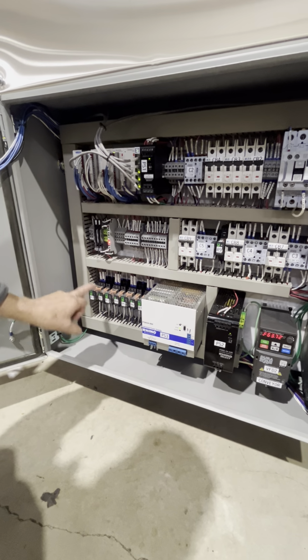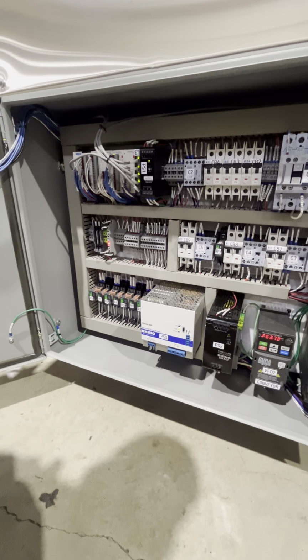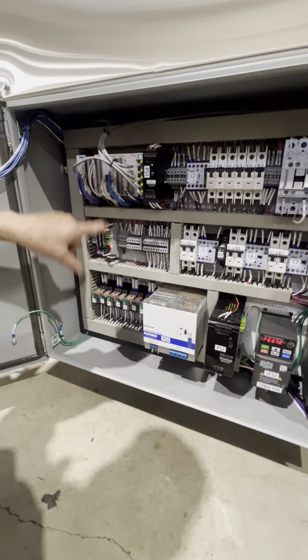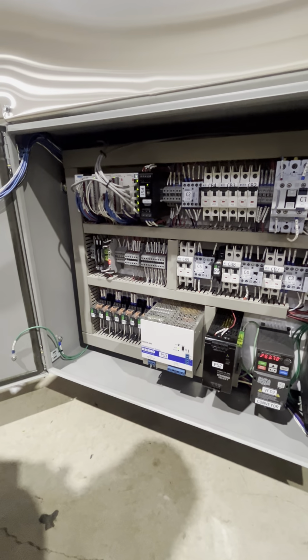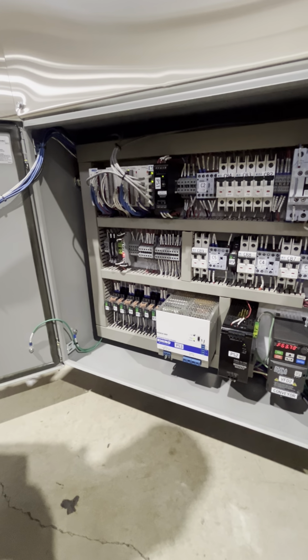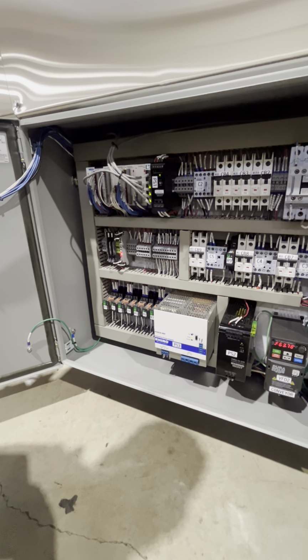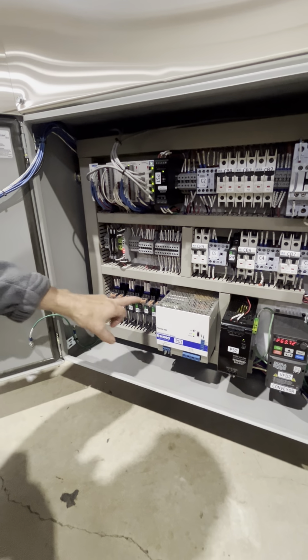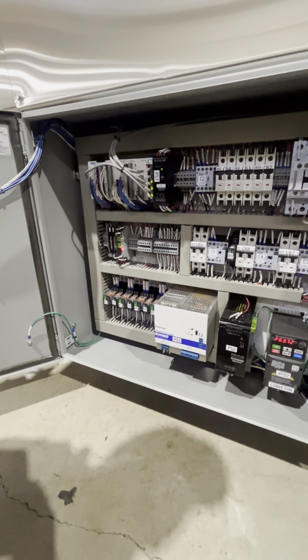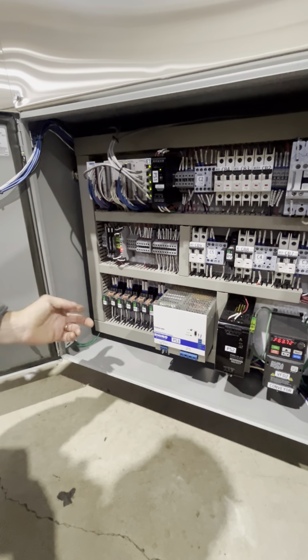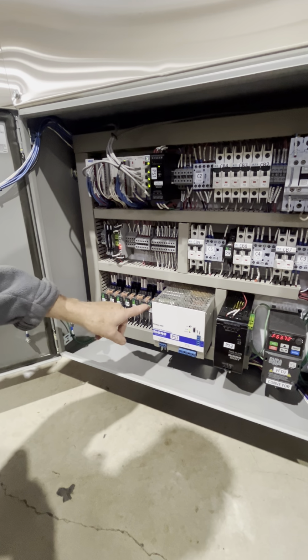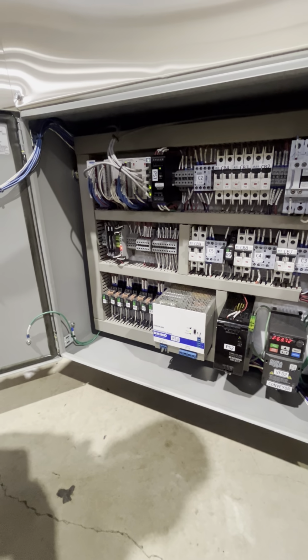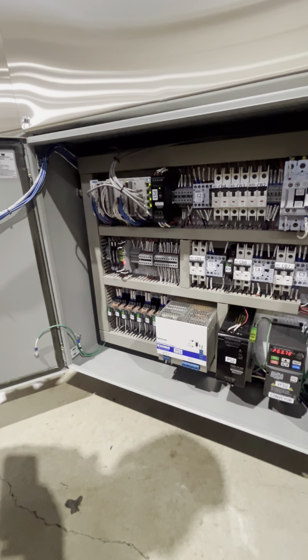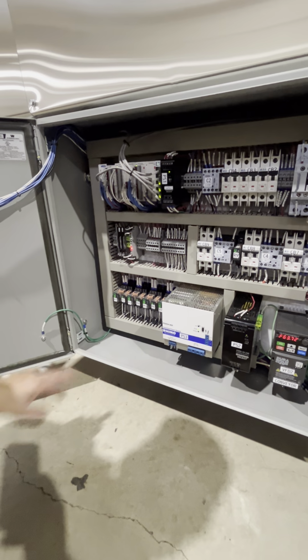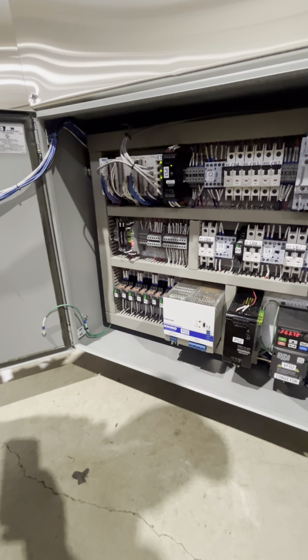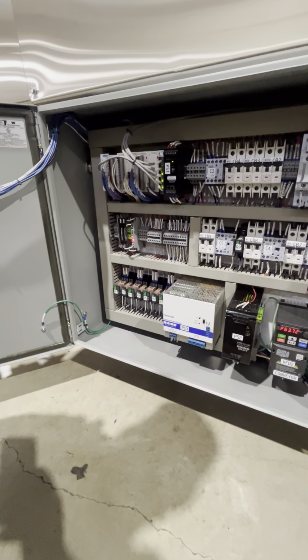We have a bunch of relays here. These relays are just labeled 1 through 8. They are 8 outputs off of the output module. The modules here typically are only good for about less than an amp, and most of our load is significantly more than an amp. So the output powers up a relay, and the relay itself powers the device that you're working on. At any time, these have a manual override on them, for troubleshooting purposes. Obviously this would just be for an electrician or somebody who's pretty well versed in it. You can manually override one of these if you're doing some kind of troubleshooting.